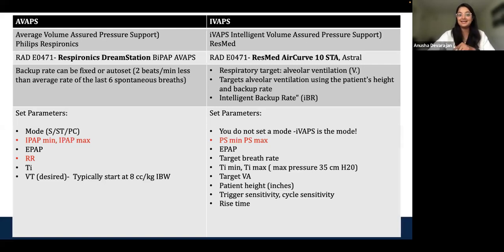So we need to do the math there to make sure we actually set a pressure support min and pressure support max. A lot of things will stay the same in terms of the EPAP. The respiratory rate helps us with the backup rate. The TI, however, is set in the ResMed, and it complicates the whole deal because we have to set a TI min and a max. But keep in mind that these home devices don't give us pressures of greater than 35. So we can do anything, but we cannot recommend pressures greater than 35.